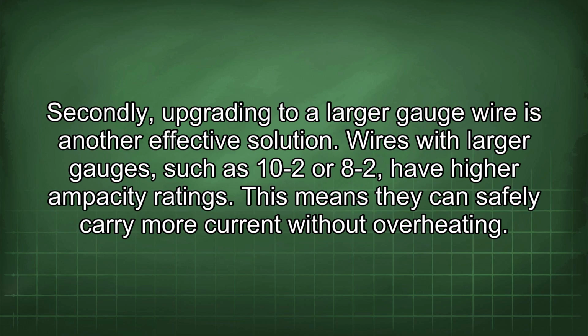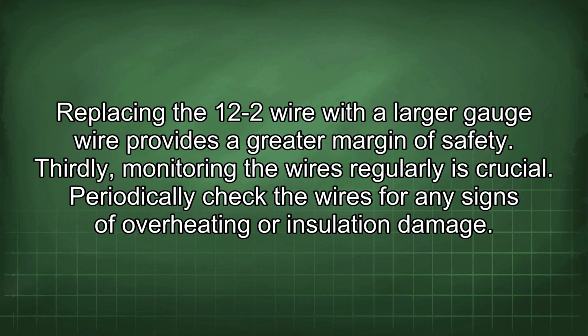Secondly, upgrading to a larger gauge wire is another effective solution. Wires with larger gauges, such as 10-2 or 8-2, have higher ampacity ratings. This means they can safely carry more current without overheating. Replacing the 12-2 wire with a larger gauge wire provides a greater margin of safety.